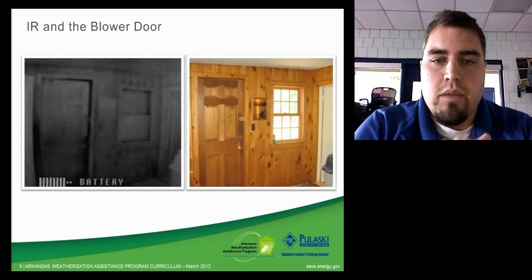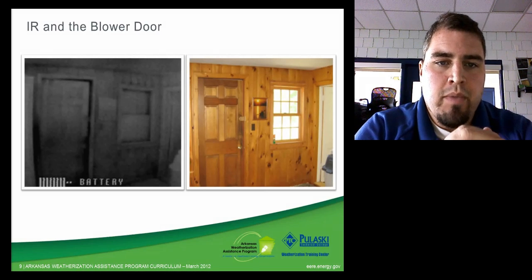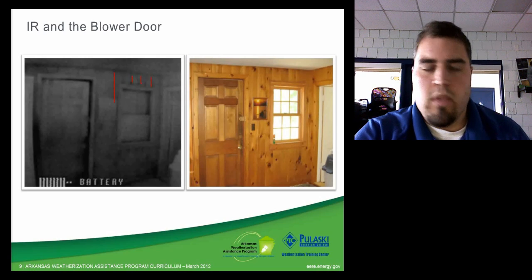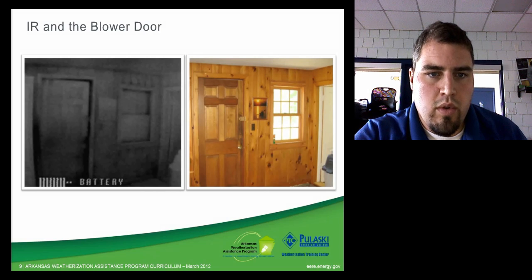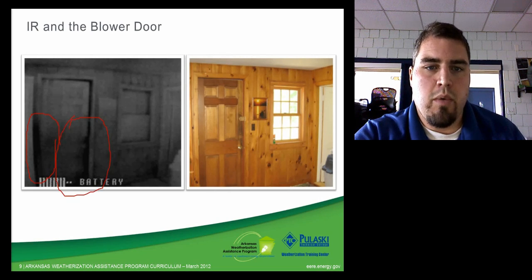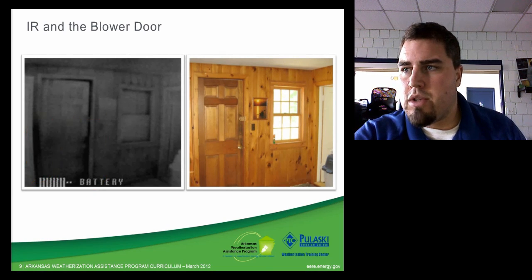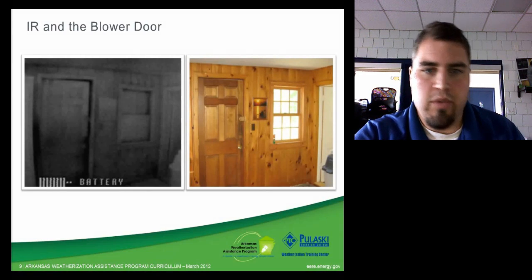This is what we call matchstick down here. It's typical tongue and groove pine paneled walls. We notice here on this picture at the edge of every single board we've got infiltration. Every single board's got infiltration on it. And then also I want you to look here on the door. See how dark it is here around the door? Do we think that weather stripping is working very well? Probably not, having that much infiltration around the door. From the picture, it looks like the door is actually an in-swing. So we've got a lot of infiltration coming around that door.